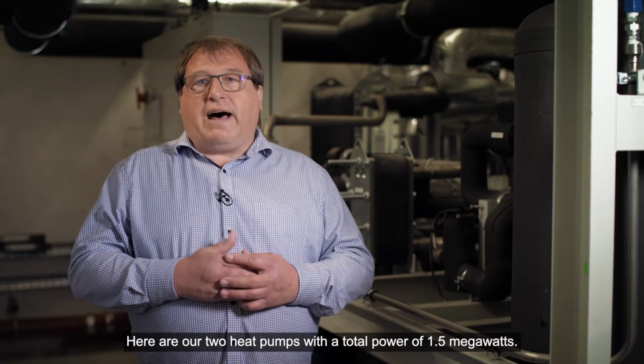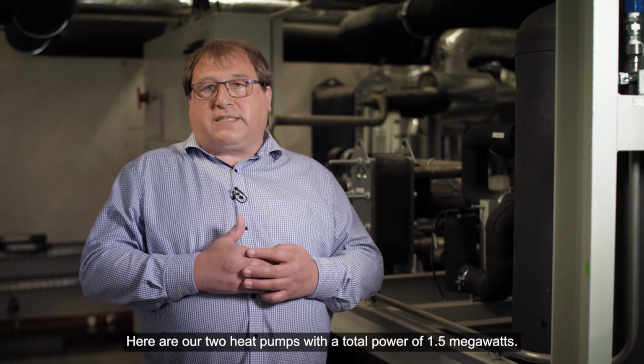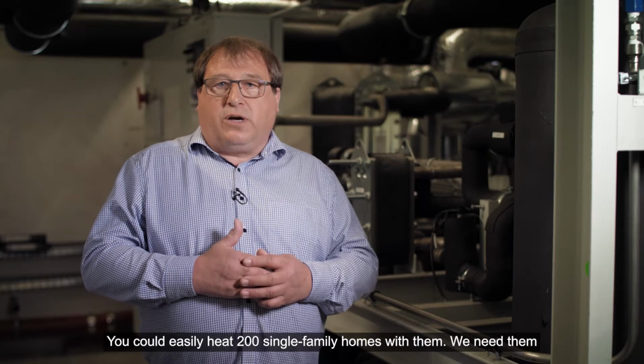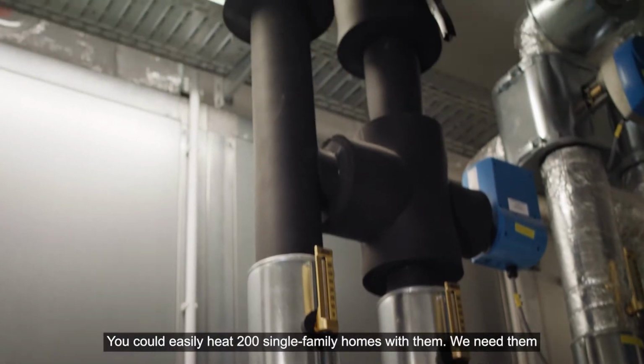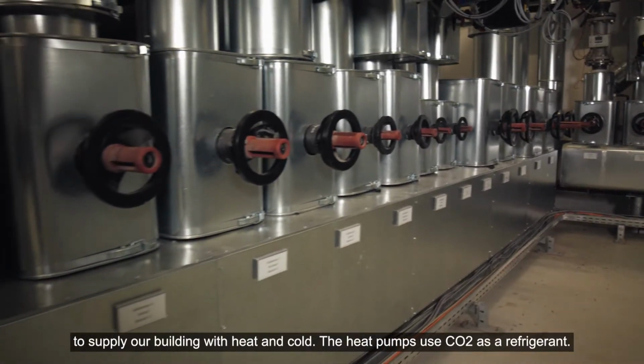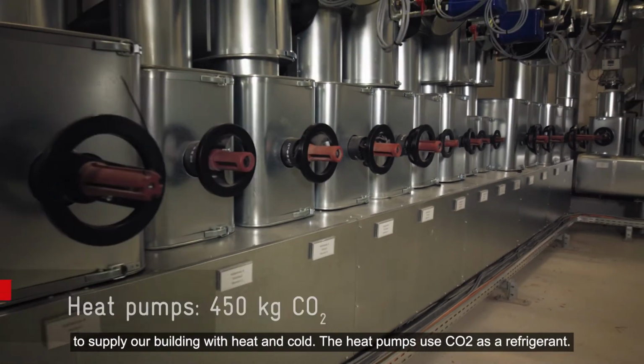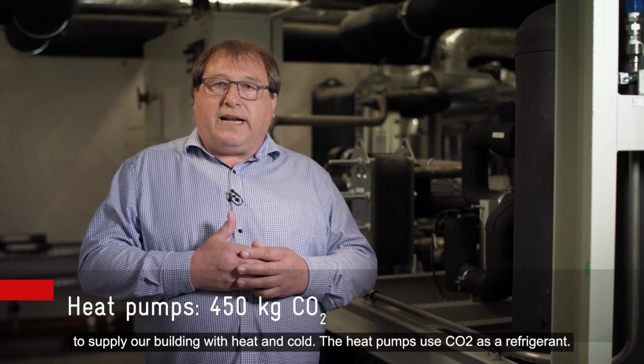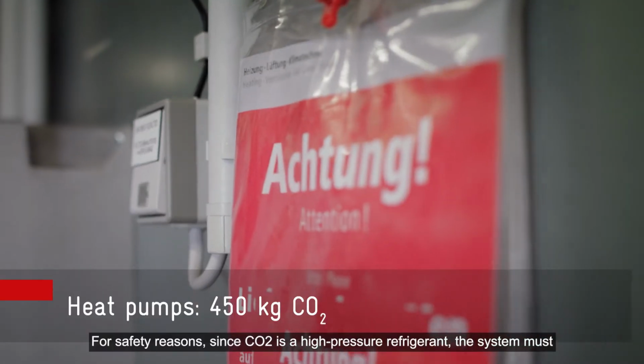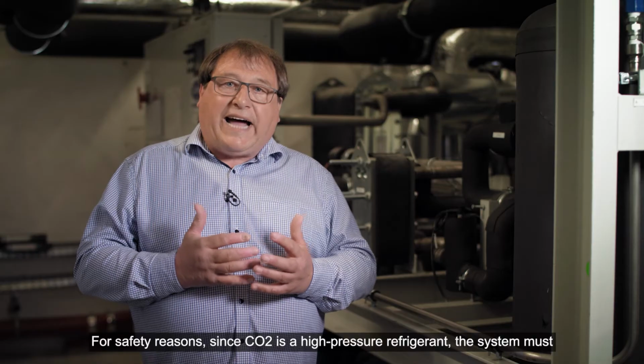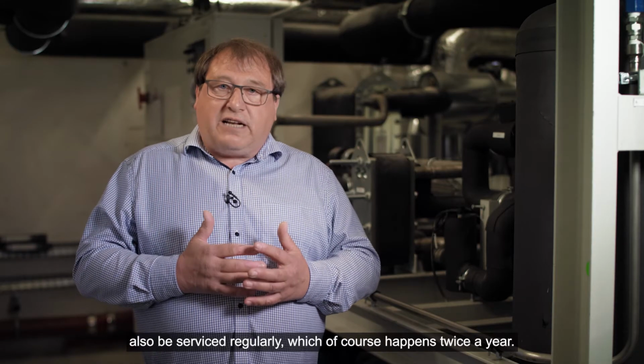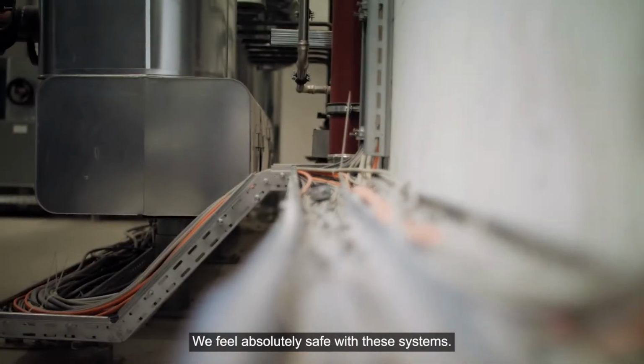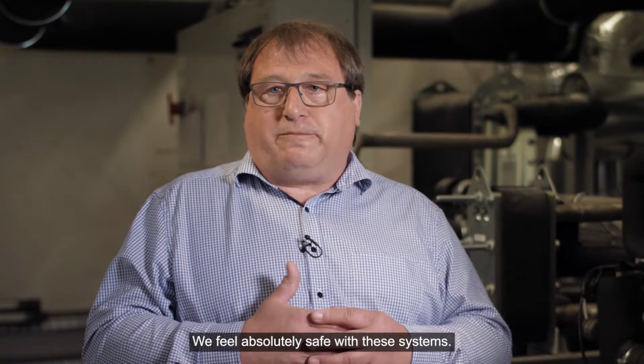Here are our 2 heat pumps with a total power of 1.5 megawatts. You could easily heat 200 single-family homes with them. We need them to supply our building with heat and cold. The heat pumps use CO2 as a refrigerant. For safety reasons, since CO2 is a high-pressure refrigerant, the system must also be serviced regularly, which of course happens twice a year. We feel absolutely safe with these systems.